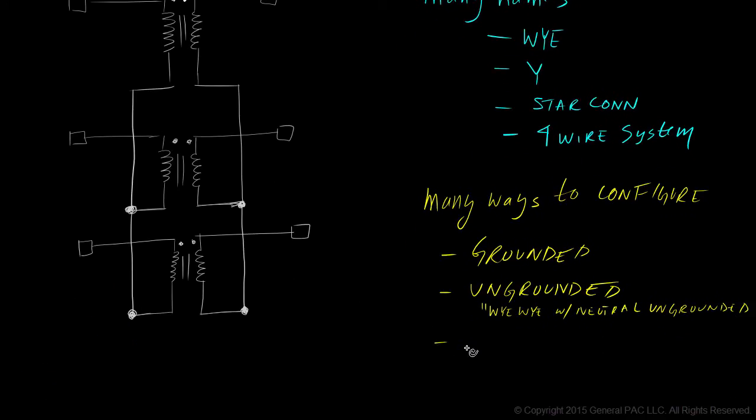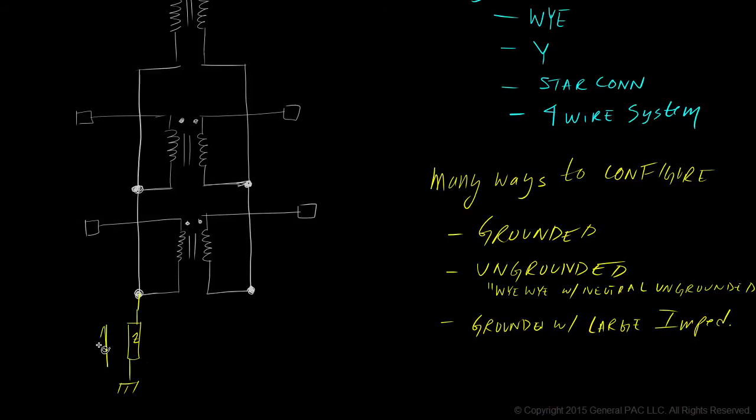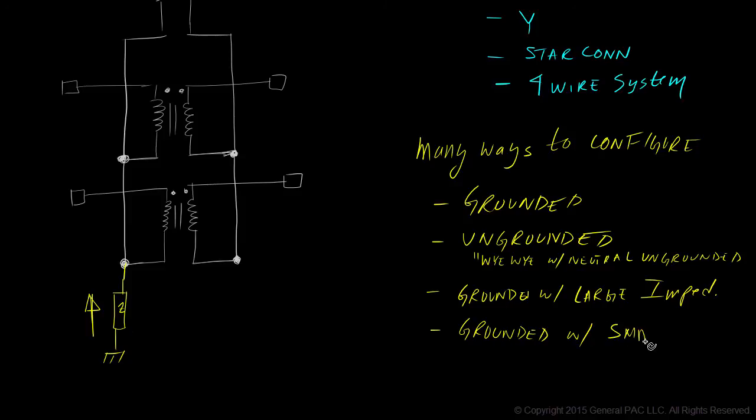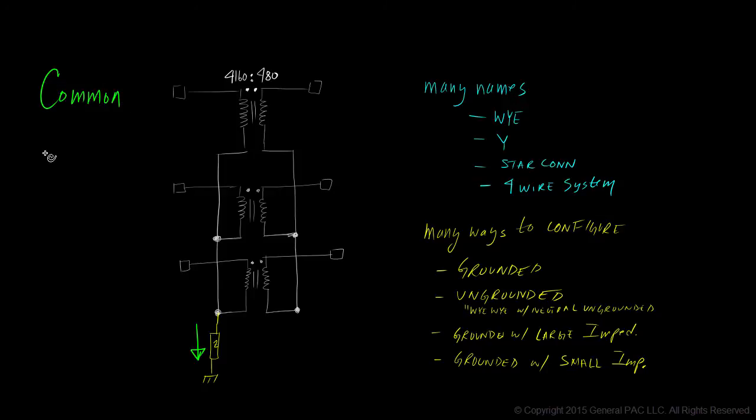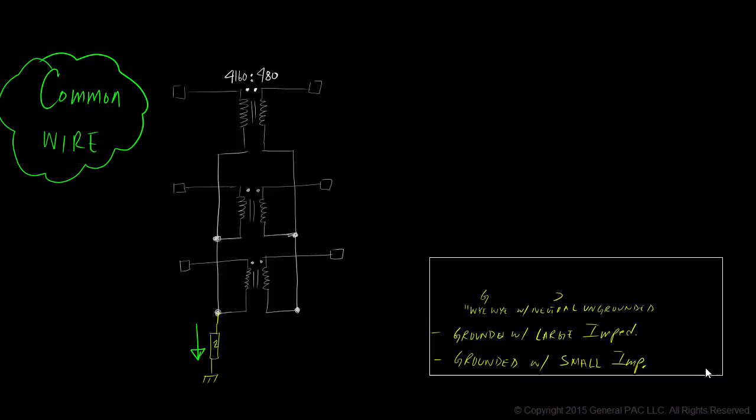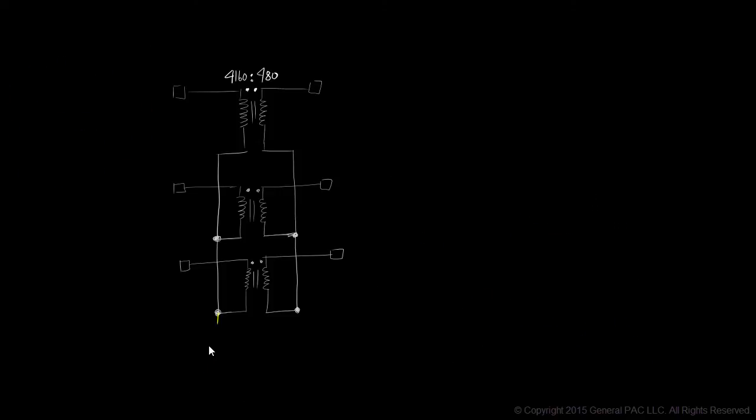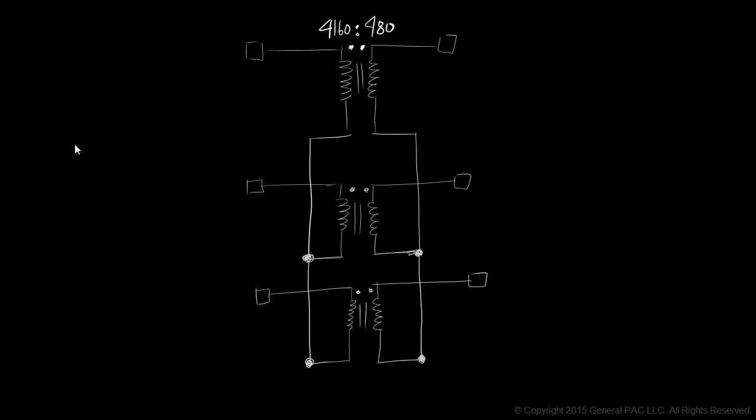Sometimes the fourth wire is grounded with a very large impedance like this. And sometimes it's grounded with a small impedance. Nonetheless, a four-wire system is distinguished by a common wire that connects all three windings together to a common point. In our example, we'll keep our discussion simple and solidly ground both sides of the transformer.